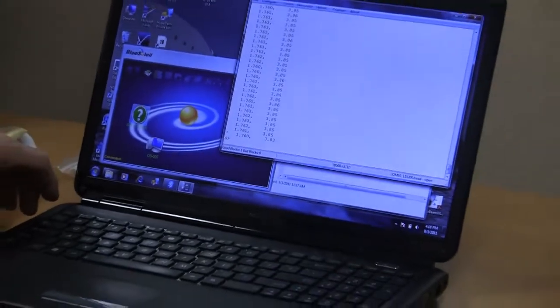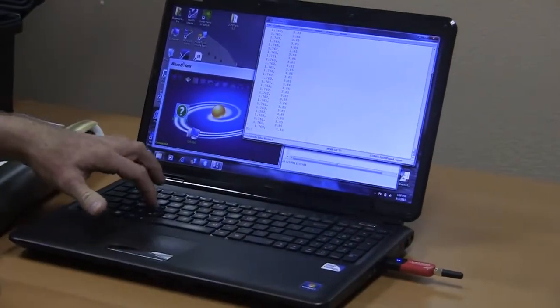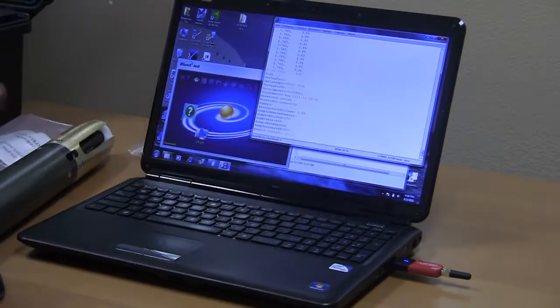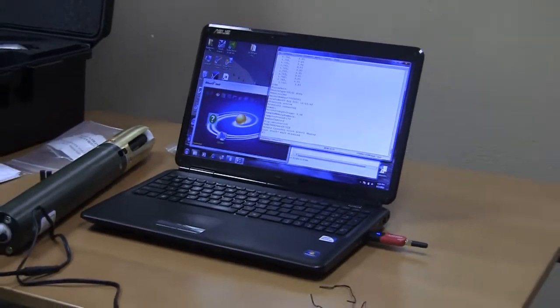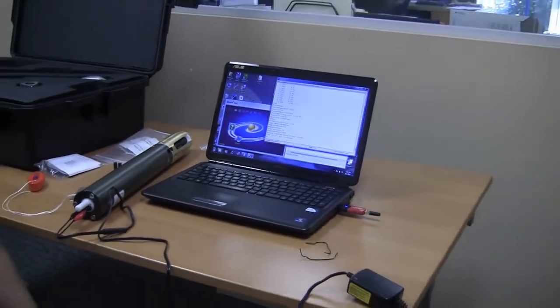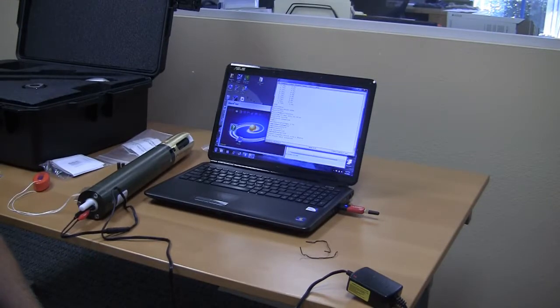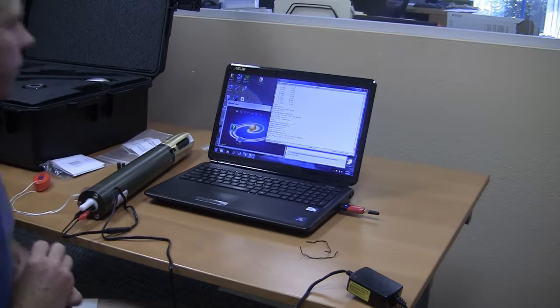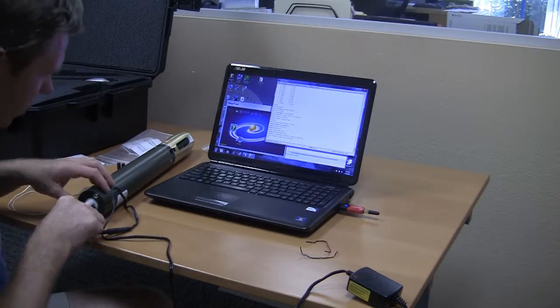If you press the escape key, that interrupts the command, and you're back in the terminal window. If you accidentally disconnect while this real-time streaming command is happening, the probe will automatically terminate the command after 2 minutes of inactivity. So after 2 minutes, you can just reconnect to the probe again. So this is how you charge the probe.